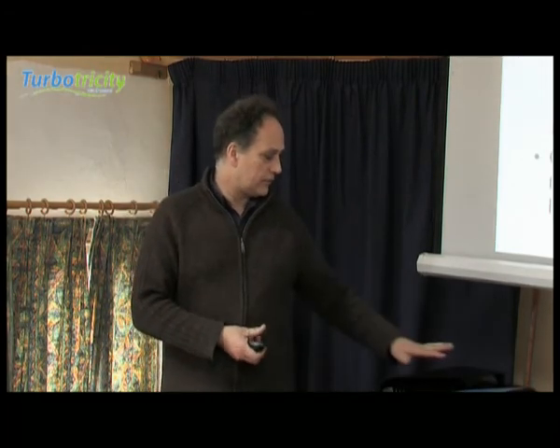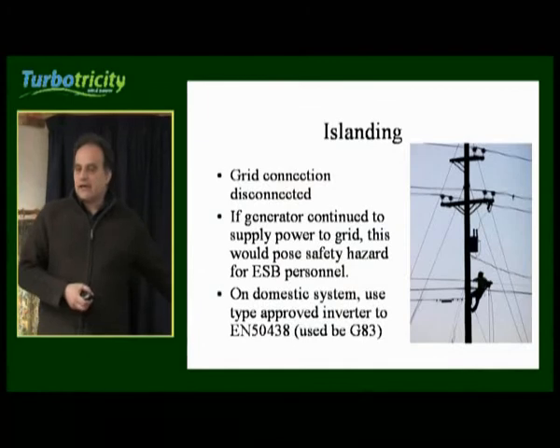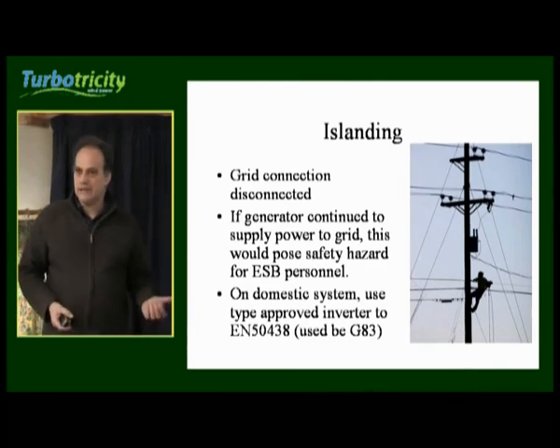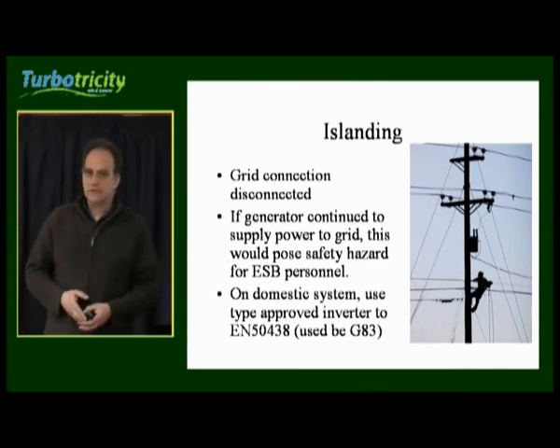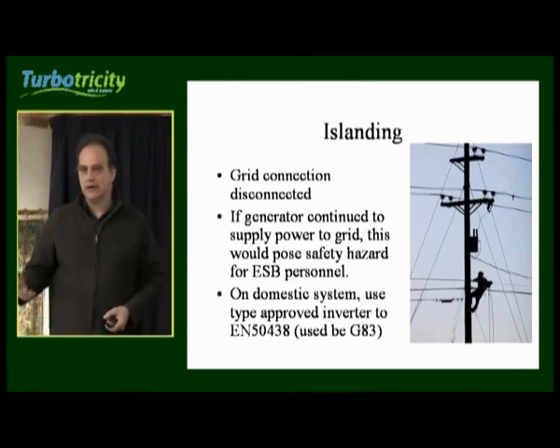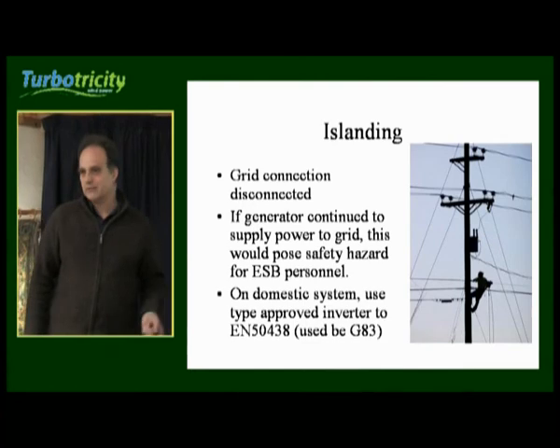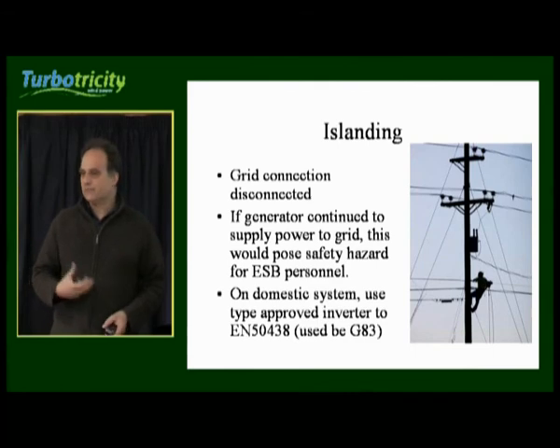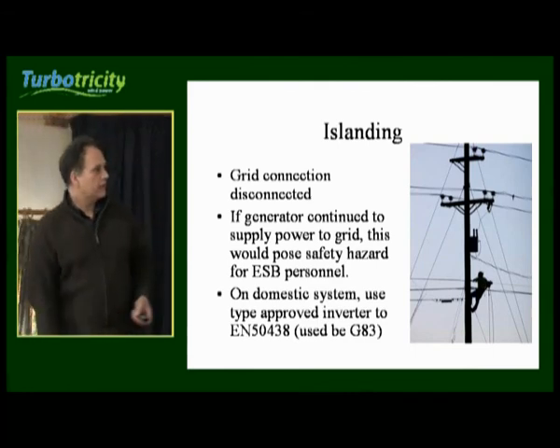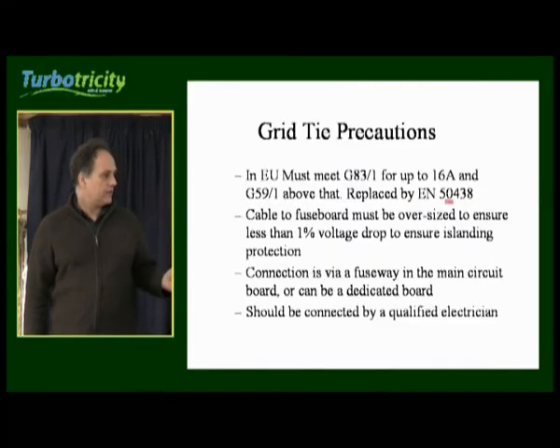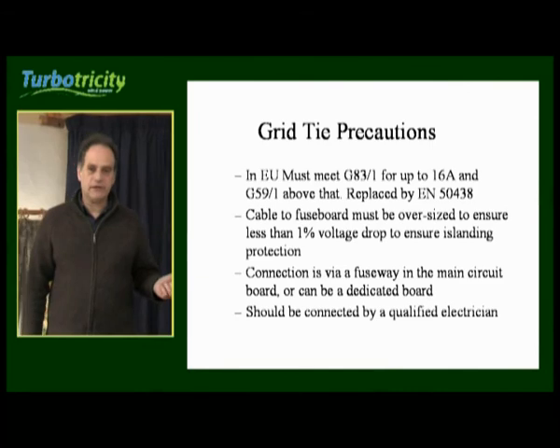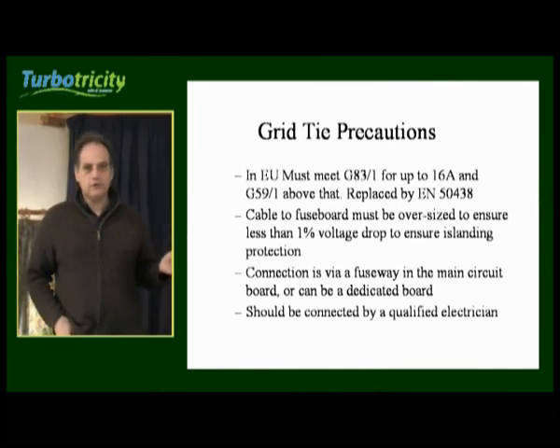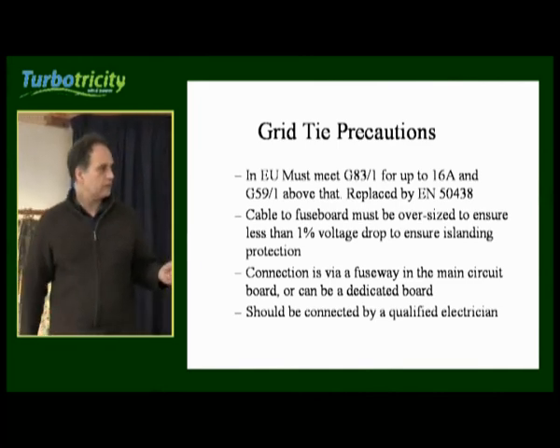There are certain standards these inverters must meet. One of them relates to islanding — where the grid is disconnected, they must shut off within half a second. That's because if ESB workers are working on lines and think they've switched off the power, you'd otherwise be feeding 240 volts into it and could kill them. There are always very strict safety regulations on these inverters, including a cut-off time. This is part of the standards determined by EN 50438, which is the new European standard that applies in Ireland. Your inverter must meet whichever standard your local utility company is insisting on.